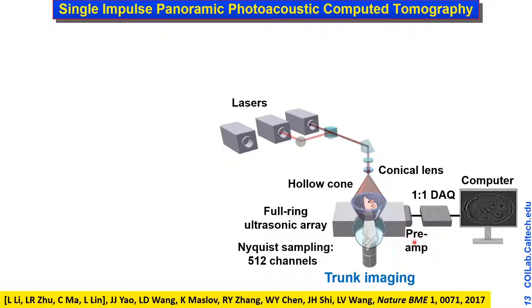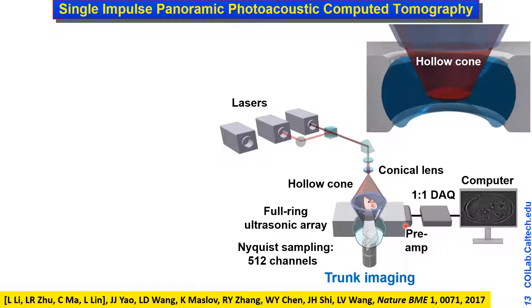As soon as sound is converted to electrical signals, we preamplify to minimize noise pickup and maximize SNR. With one-to-one data acquisition and a single laser shot, we acquire a 2D image within a few microseconds — one of the fastest imaging modalities available. The imaging acquisition time is limited by the acoustic transit time across the field of view. For brain imaging the system is reconfigured using a diffuser to generate a solid beam, which is the optimal illumination pattern.